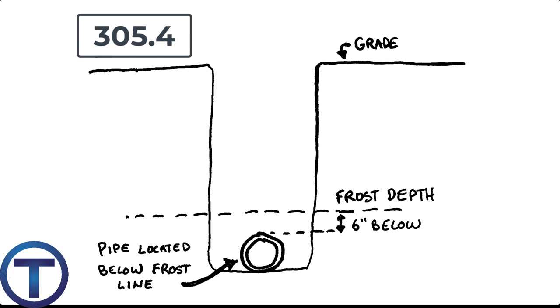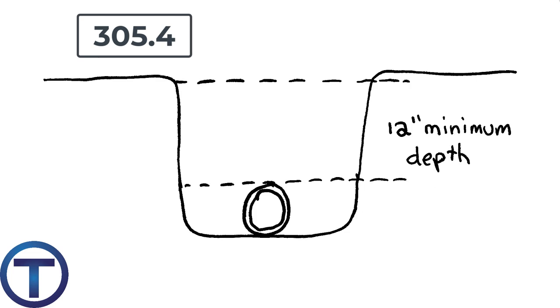305.4 talks about protecting pipes against freezing. We have to dig down past the frost line — code says you have to be six inches below that frost line. Generally, if you're about four feet deep in Cache Valley, you're deep enough to avoid freezing. In southern Utah, St. George, Arizona, or places where you don't get much frost, the pipe should be no less than 12 inches below the finished grade. Those are important numbers to have marked in your book.